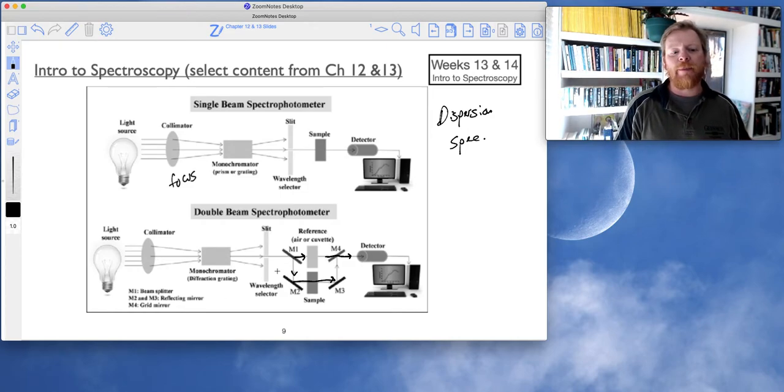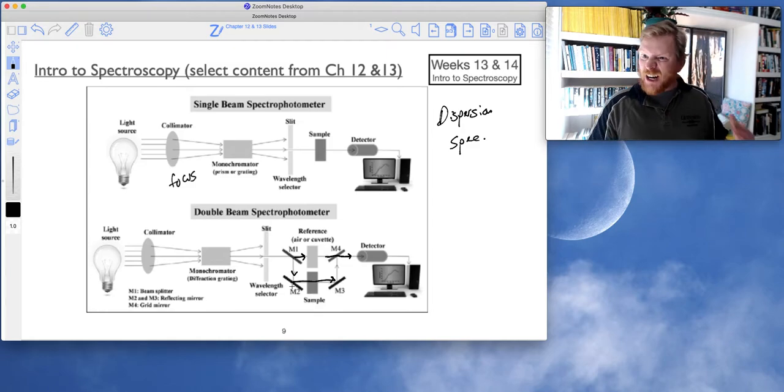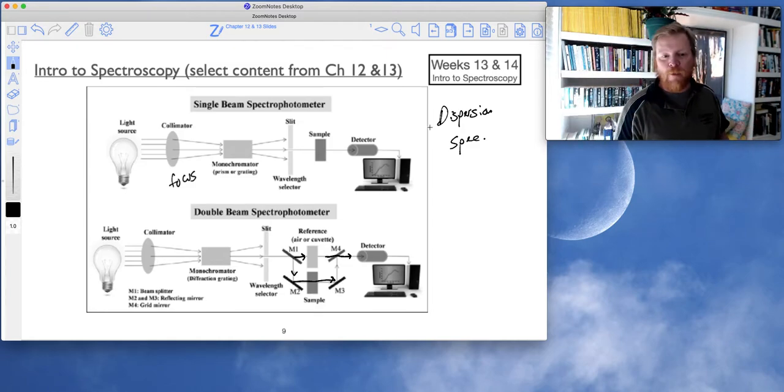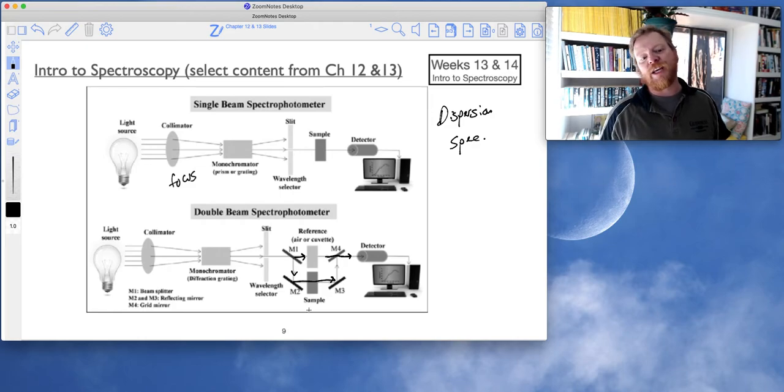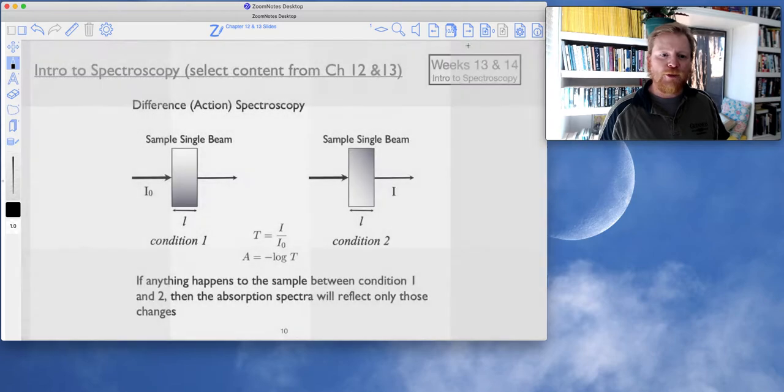So if you have a double beam instrument, these things are great. These things are very easy to use. You typically don't have as much background sample issues. If your background and sample weren't identical, with the exception of the analyte molecules, then you have less of those issues with the double beam instrument.